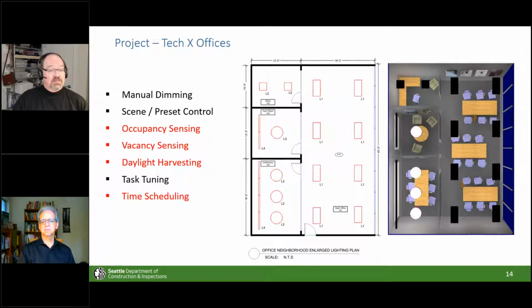The easiest way to think about this is the head height of the window—in this case 9 feet—with the room 18 feet deep, giving us two daylight zones. The first row of fixtures closest to the window is the primary daylight zone; fixtures farther from the wall are the secondary daylight zone. At the very least, these must be controlled separately based on daylight controls.